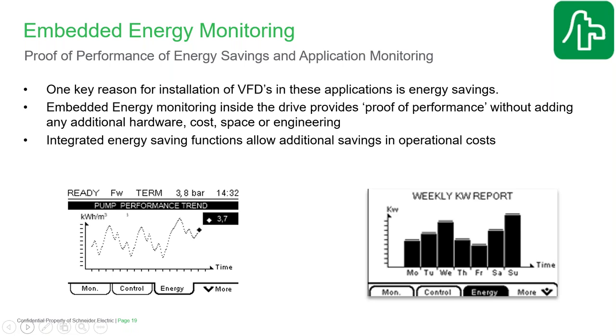If we're looking at the trending values that come from it, you see from that little chart on the left, these are screenshots from the drive, so you can view this data directly from the drive as well as through remote systems. You can see there we've got a repeated pattern of energy usage as the pump is running to serve different irrigation needs at different times of day. You can see that pattern repeats, but in that last cycle it seems to be changing. We're using more energy. That we can use as a means of interpreting and analyzing the data. We can tell something's changed in how this pump application is working.